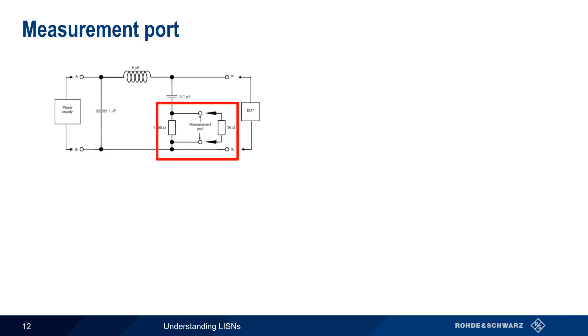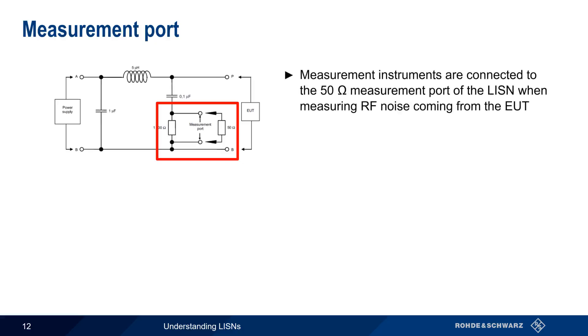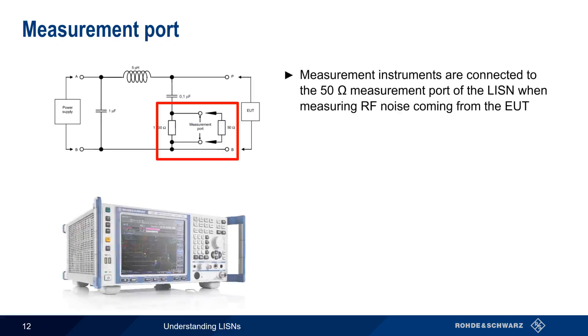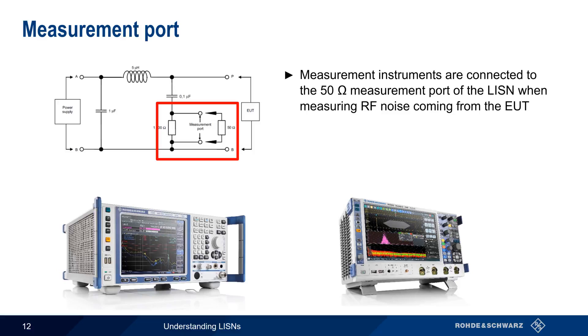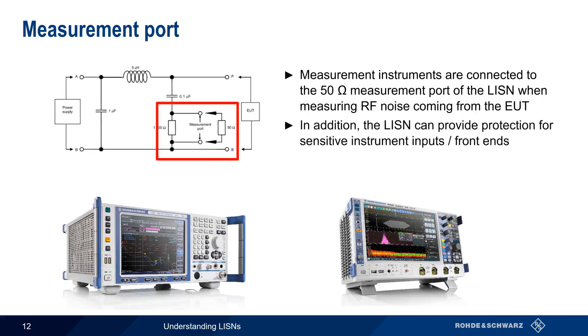The third primary function of a LISN is the measurement port. This 50 ohm port is used to connect a LISN to a measurement instrument, such as an EMI receiver or an oscilloscope, in order to measure conducted RF signals produced by the EUT. In addition to this measurement function, the LISN can also provide various types of protection to the sensitive inputs or front ends of measuring instruments.